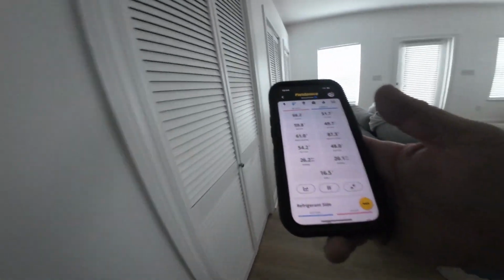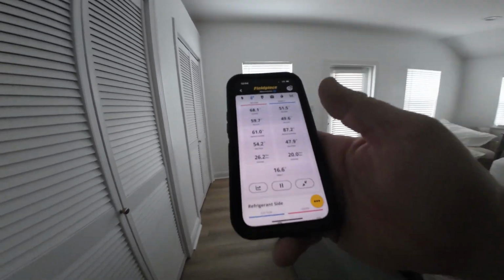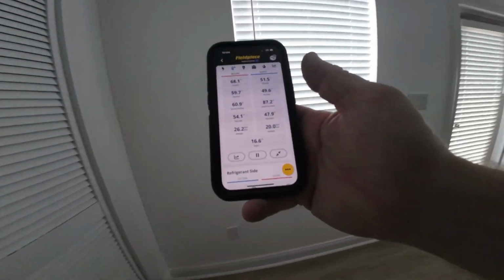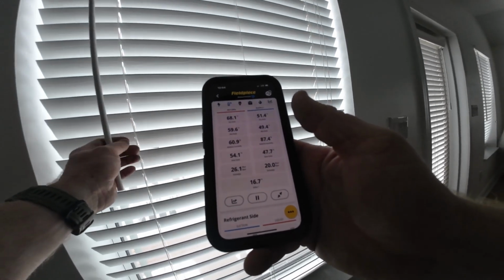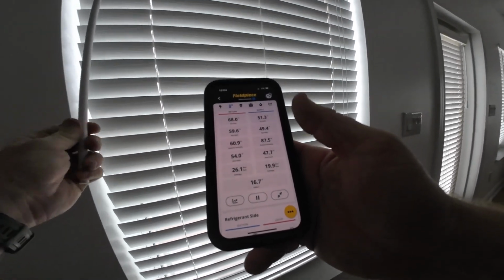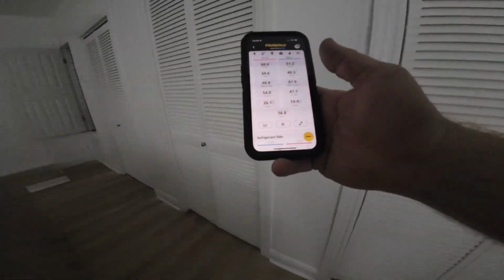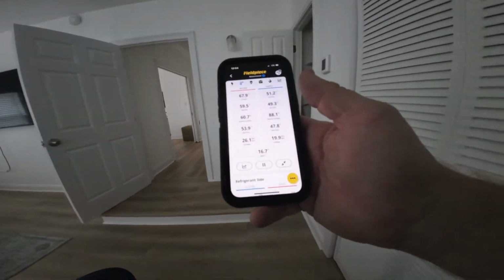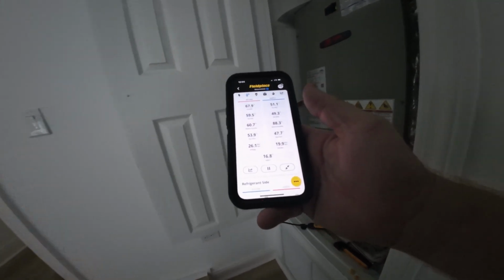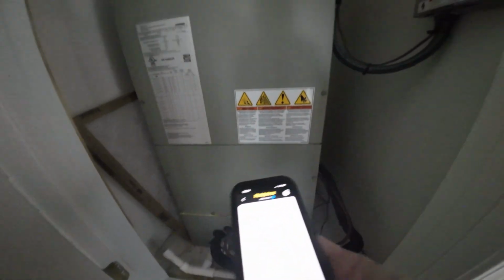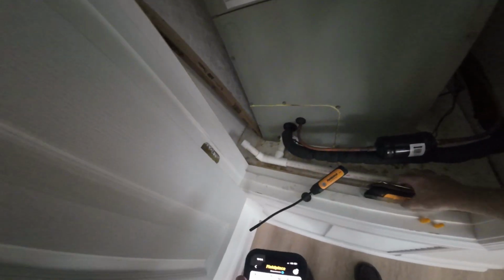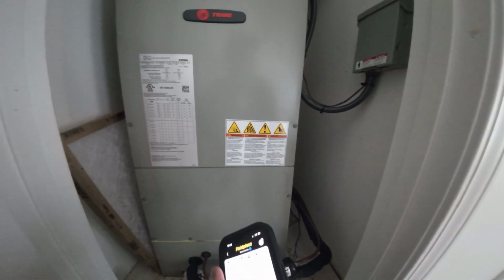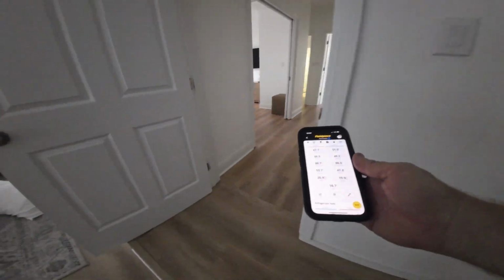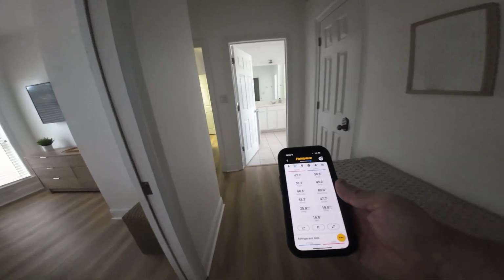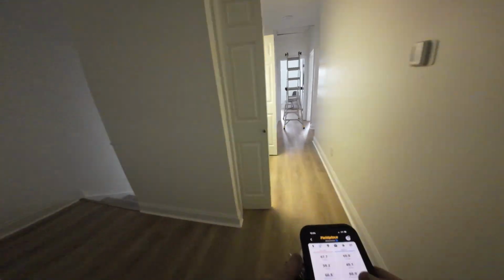We're at 16 degrees, which is bare minimum. About 15 to 20 is a rule of thumb, like back in the day, or 22. My rule of thumb I like to go by is 18 to like 22, 20 being pretty much perfect. And right now it's not performing that great, so I'm gonna go check the pressures and then we'll come back to this and see what's going on. Apparently we just checked all this and it was good to go, running as designed, so let's go back out and see what we got going on.